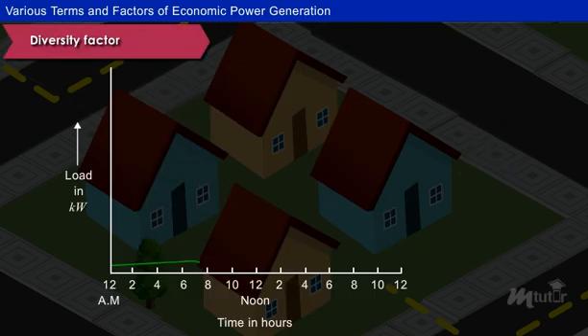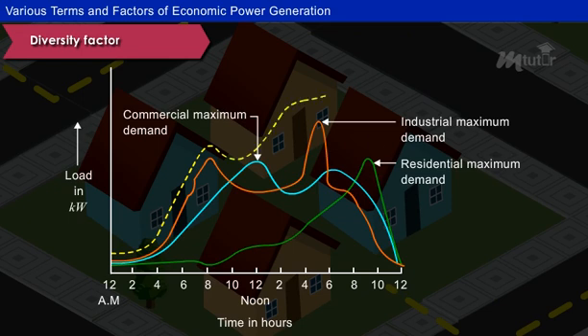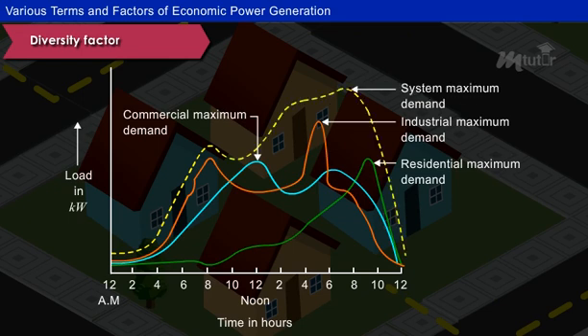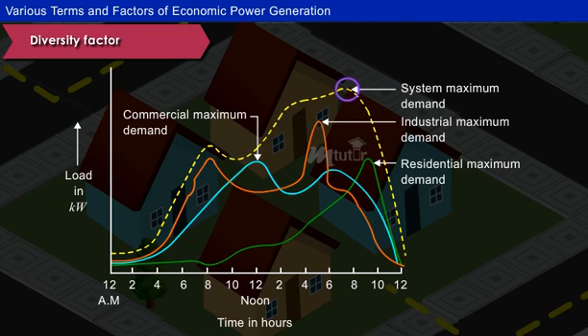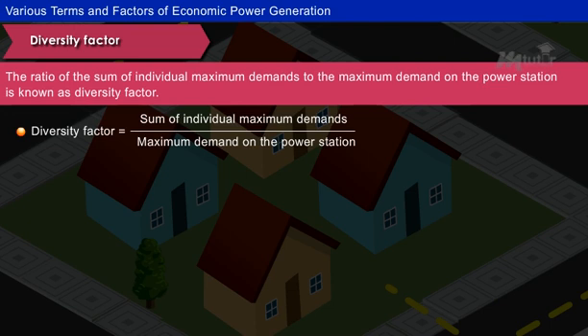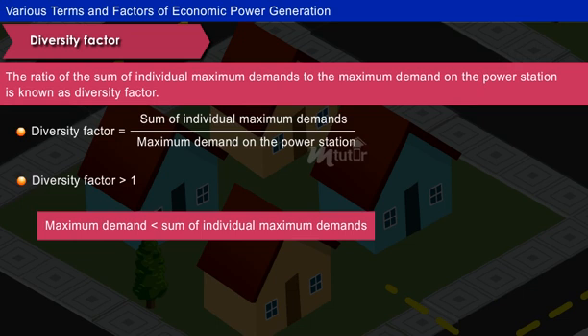Diversity Factor: A power station supplies power to various types of consumers whose maximum demands generally do not occur at the same time. Hence, there is a difference between the individual maximum demand on the station and the sum of consumers' maximum demands. This is called diversity in individual consumers' demand. So, the ratio of the sum of individual maximum demands to the maximum demand on the power station is known as diversity factor. The diversity factor is always greater than 1 because maximum demand on the power station is always less than the sum of individual maximum demands of the consumers.